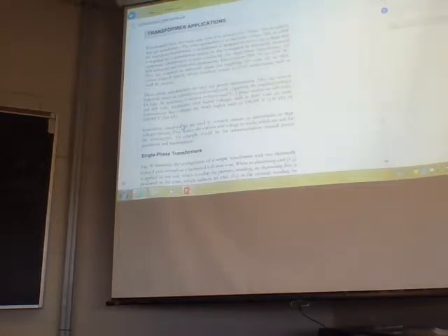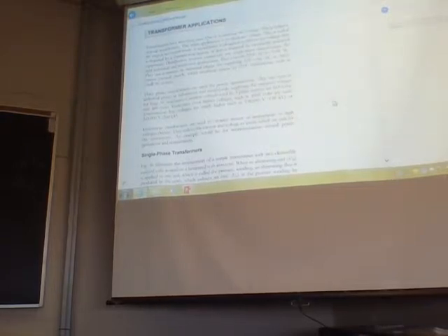Instrument transformers are used to connect meters or instruments to high voltage circuits. They reduce the current and voltage levels to levels which are safe for the instruments. An example would be for instrumentation on power generators and transformers. Hydro One uses instrument transformers for the metering of this electrical service and building. They use current transformers and power transformers that see how much current is being used at the higher voltage, but the lower voltage transformers allow the meter to record what's being used power-wise.